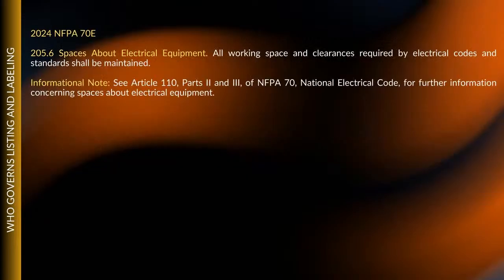When you look at NFPA 70E, the first thing I wanted to point out is Chapter 2, Section 205.6, which basically goes back and forth. It says all working space and clearances required by electrical codes and standards shall be maintained, and references you over to Article 110 of the National Electrical Code, Parts 2 and 3. I just want everybody to know that 70E recognizes spaces about electrical equipment to get it started.